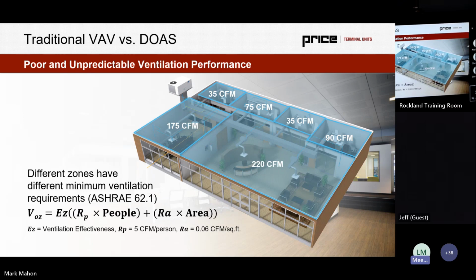If we were looking at a classroom, that would move up to 10 CFM per student and per teacher per person, mostly students, and 0.18 CFM per square foot. So yes, the built environment cares a lot more about kids than it does about us, and that's okay.